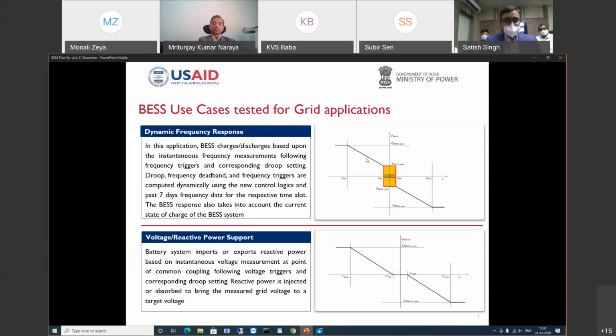These ramps, if you see here, are the rate at which you want to discharge the batteries. These are the parameters which we can fine tune. And after a threshold value, say from here, if I say that my grid collapse event is going to trigger at this frequency, then I say your battery would discharge or charge at the rate of 100% of the full capacity. So those controls are there. This is a very basic kind of design, but when I go to the system, I'll explain more on what all other parameters have been considered while designing this frequency regulation module.